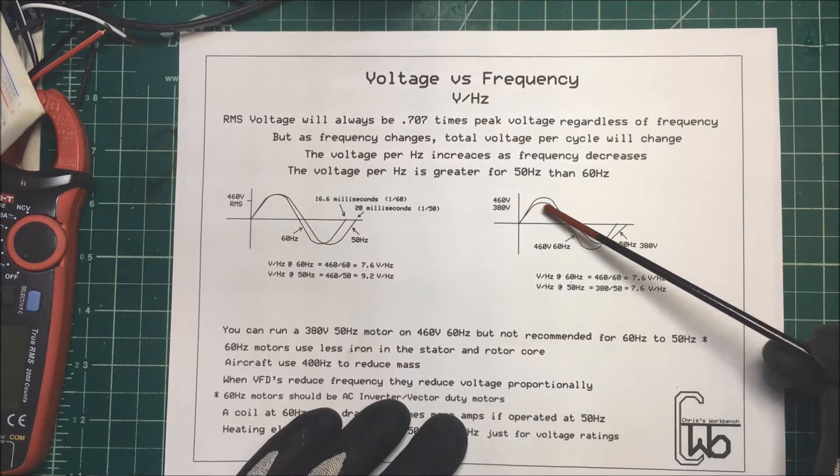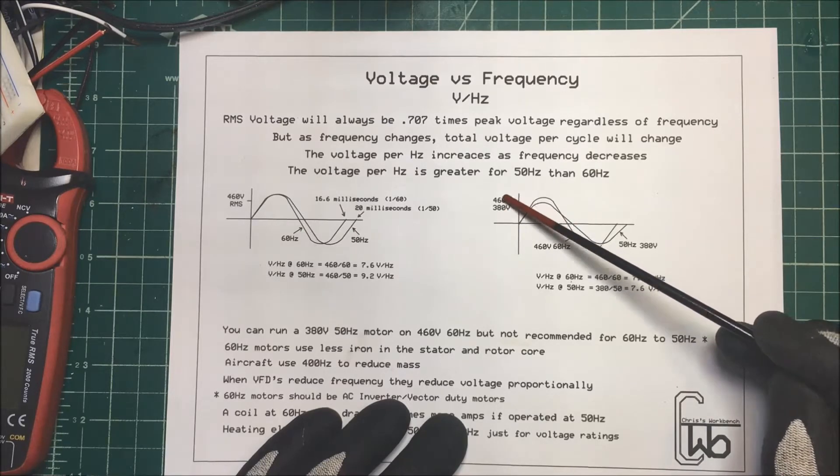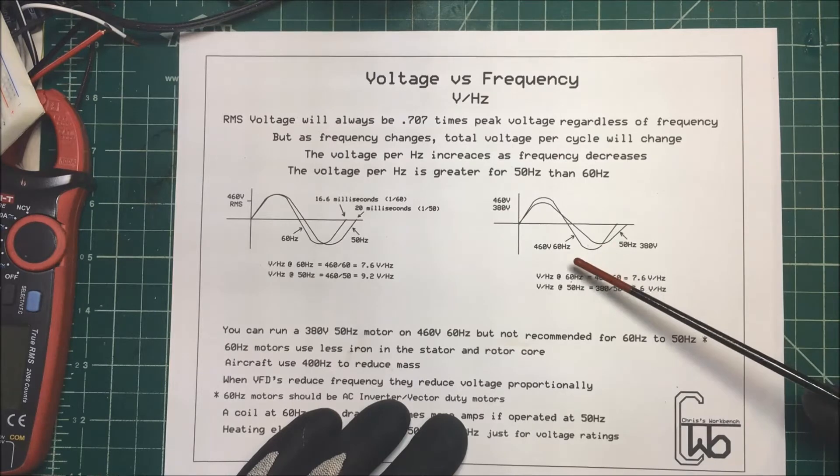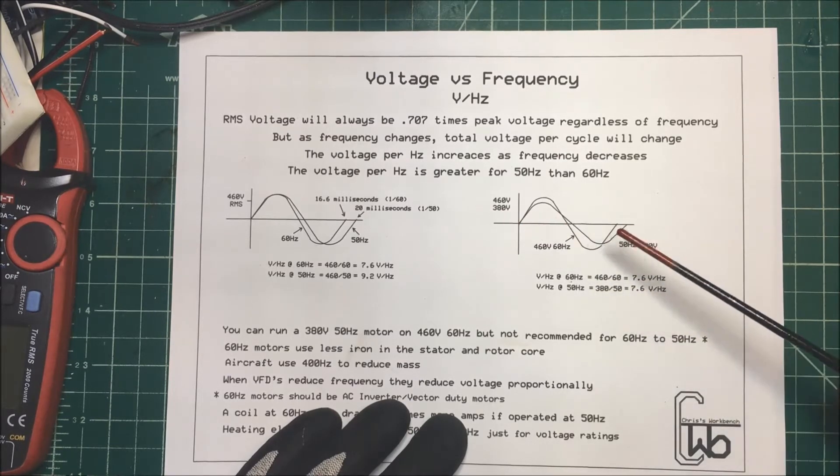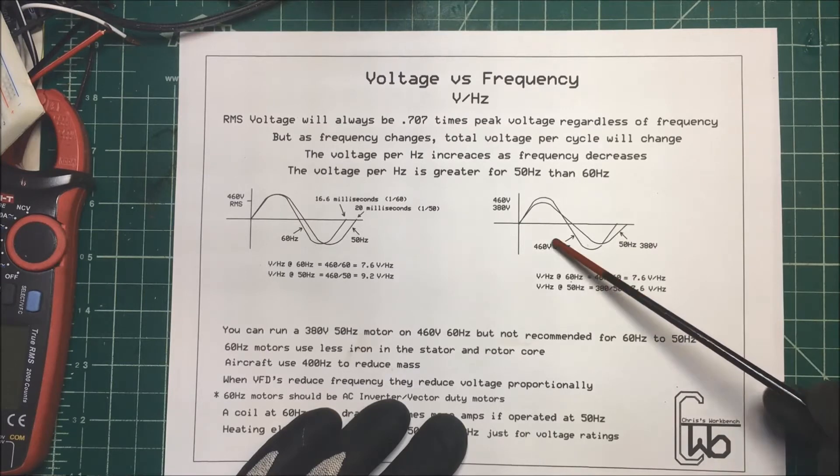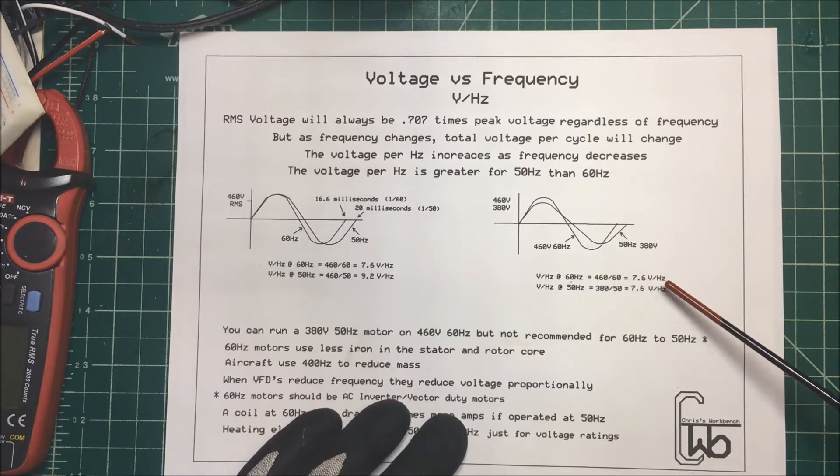Now let's take a look over here. We've got a 460 volt standard North American voltage, and then we have a 380 volt European voltage here. Now we have our two sine waves here. And if we calculate the volt hertz, of course, for 60 goes into 460, we're going to get 7.6 volt hertz.